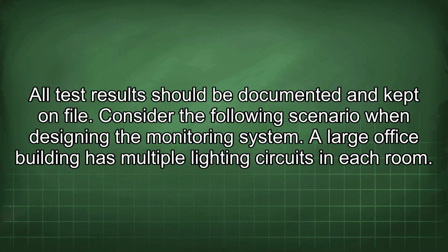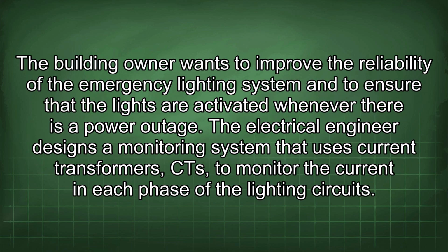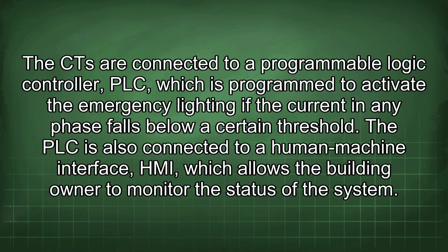Consider the following scenario when designing the monitoring system. A large office building has multiple lighting circuits in each room. The building owner wants to improve the reliability of the emergency lighting system and to ensure that the lights are activated whenever there is a power outage. The electrical engineer designs a monitoring system that uses current transformers, CTs, to monitor the current in each phase of the lighting circuits. The CTs are connected to a programmable logic controller, PLC, which is programmed to activate the emergency lighting if the current in any phase falls below a certain threshold.